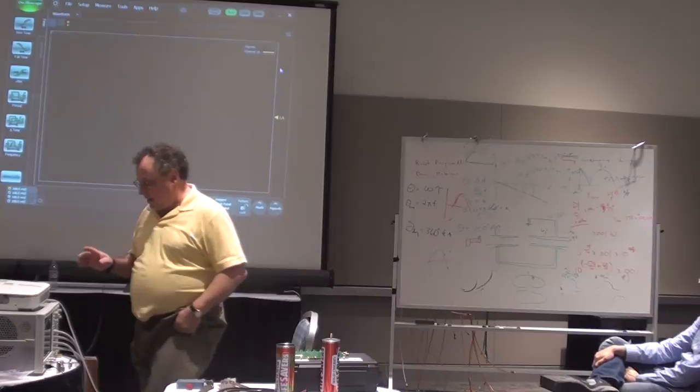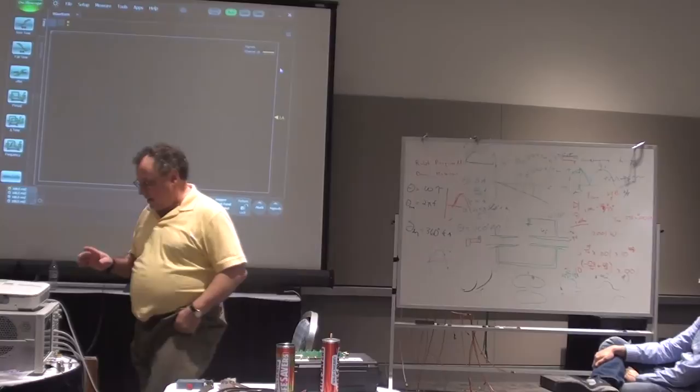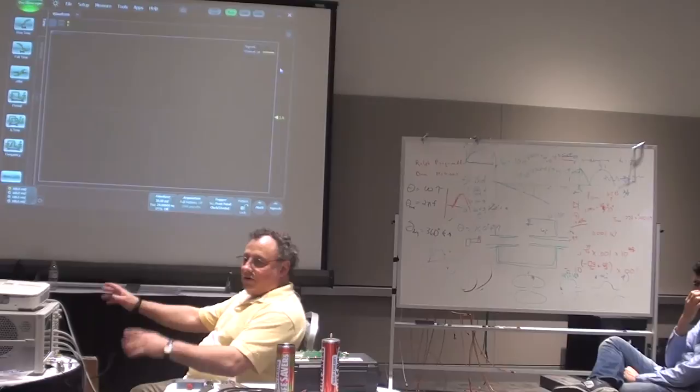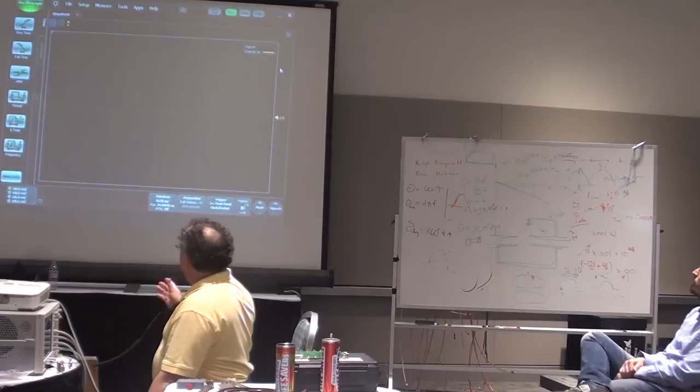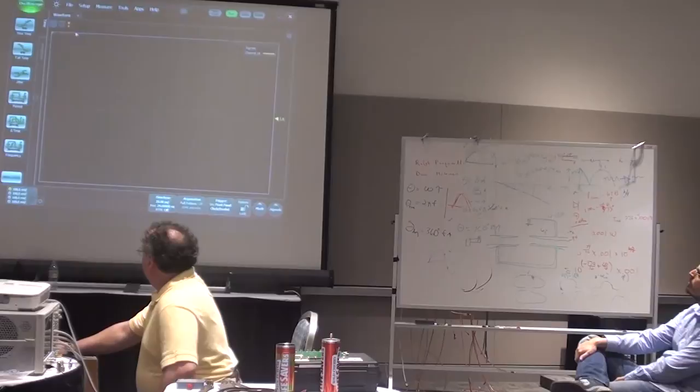So when you first turn the thing on, and you need the mouse here to monkey around a bit, and it's got a lot of other creature features in terms of save this, that, and the other. You guys can figure that out on your own. When you first turn it on though, it thinks it's an oscilloscope. Okay, and that's perfectly fine, and we don't want it in oscilloscope mode.